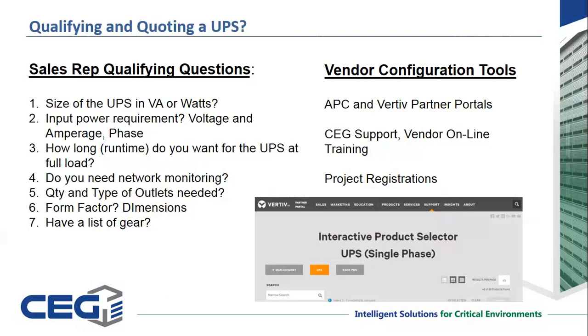On the single phase side, we're talking mostly about 120 volt input or 208 volt input. How long do you want the UPS to run at full load? So if it's rated at 10 kVA or 8 kilowatts, meaning when it's providing power at that type of load, like you've got gear that adds up to 10 kVA, how long do you want that UPS to run on battery to keep that gear up and running at full load? That's a key determination for us to figure out whether we can use the internal battery and it's going to be good enough, or do we need to start including external battery modules, and how many.